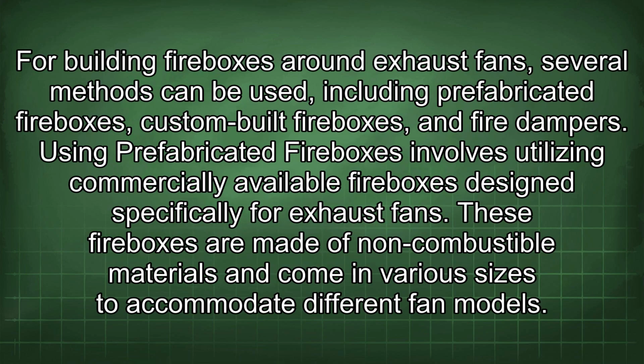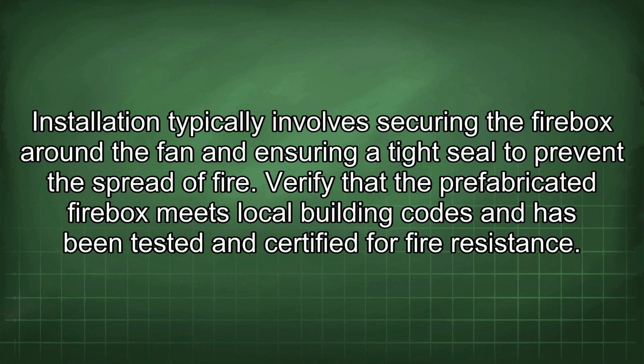For building fireboxes around exhaust fans, several methods can be used, including prefabricated fireboxes, custom-built fireboxes, and fire dampers. Using prefabricated fireboxes involves utilizing commercially available fireboxes designed specifically for exhaust fans. These fireboxes are made of non-combustible materials and come in various sizes to accommodate different fan models. Installation typically involves securing the firebox around the fan and ensuring a tight seal to prevent the spread of fire. Verify that the prefabricated firebox meets local building codes and has been tested and certified for fire resistance.